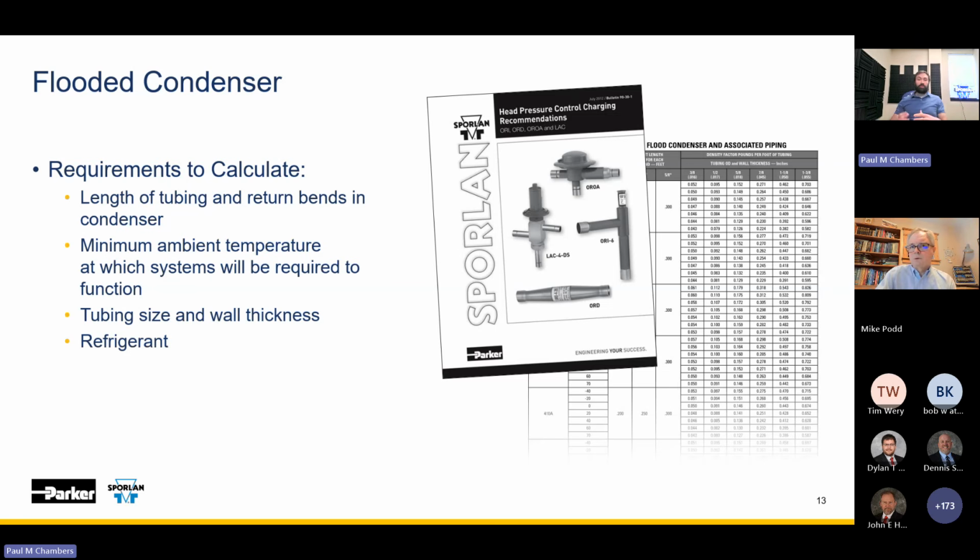So if you're setting those, charging those, that would come out of this book here, right? Where you do those calculations. So this will give you the guidance for how much flooding to put on the coil. So how much additional refrigerant is required to do the flooding.